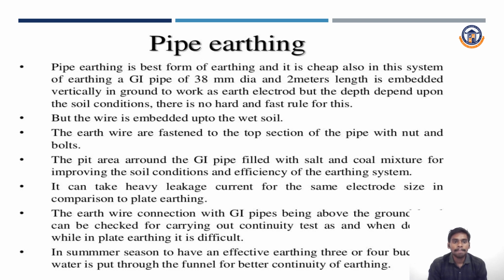Next one is pipe earthing. Pipe earthing is the best form of earthing and it is cheap also. A GI pipe of 38 millimeter diameter and 2 meters length is embedded vertically in the ground to work as the electrode, but the depth depends upon the soil condition. There is no hard and fast rule for this, but the pipe is embedded up to the wet soil. The earth wire is fastened to the top section of the pipe with nut and bolts. The pit area around the GI pipe is filled with a salt and coal mixture for improving the soil condition and the efficiency of the earthing system. It can take heavy leakage current for the same electrode size in comparison to plate earthing.